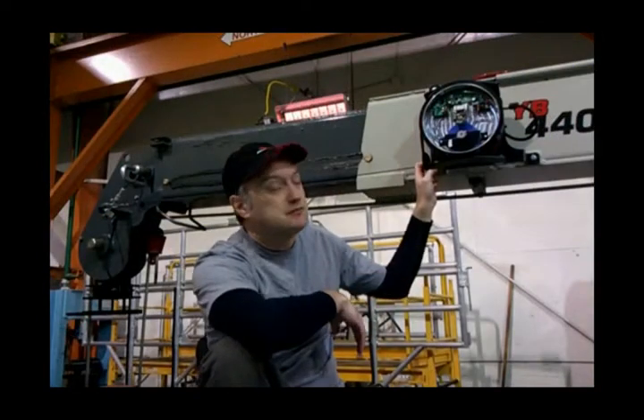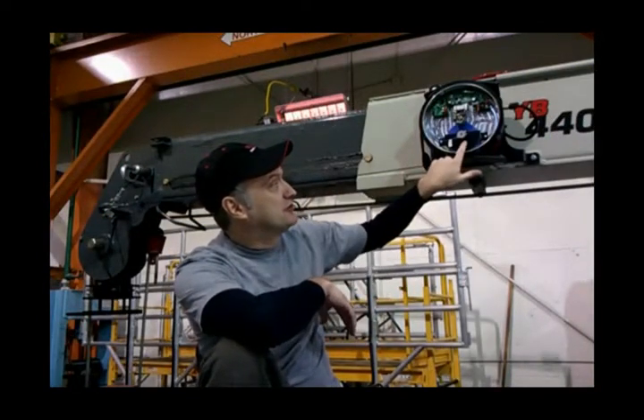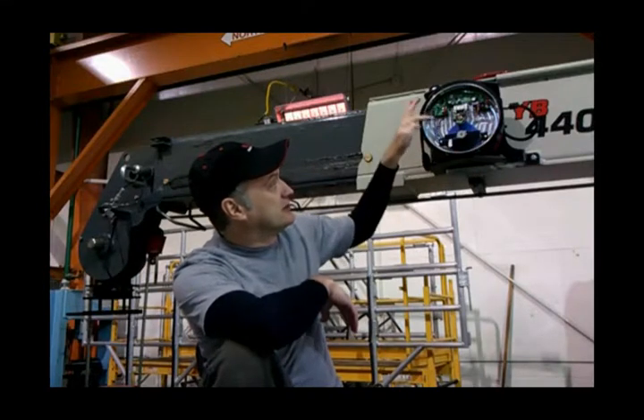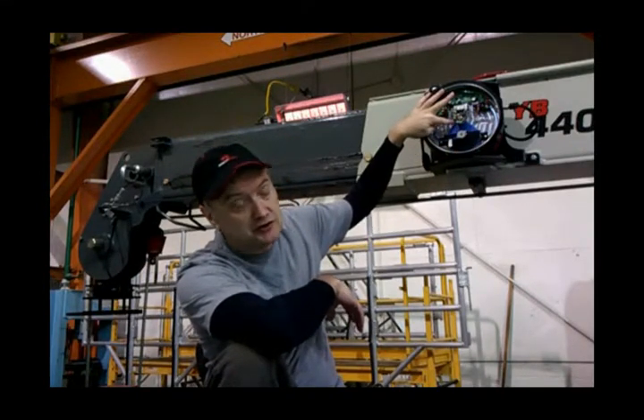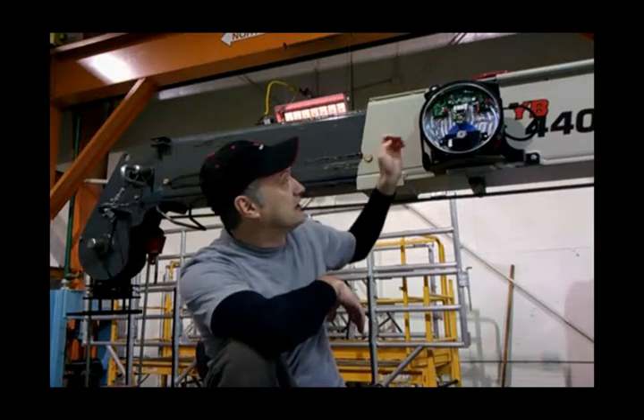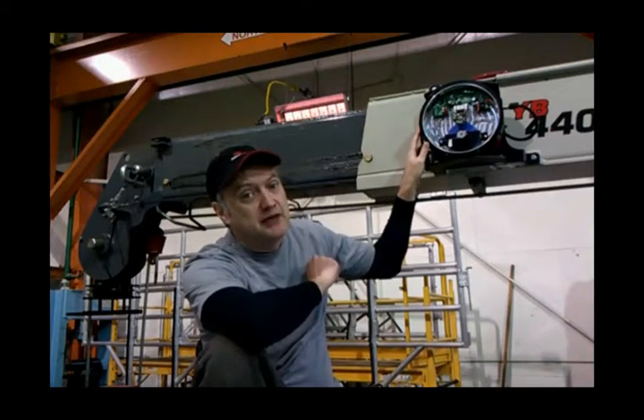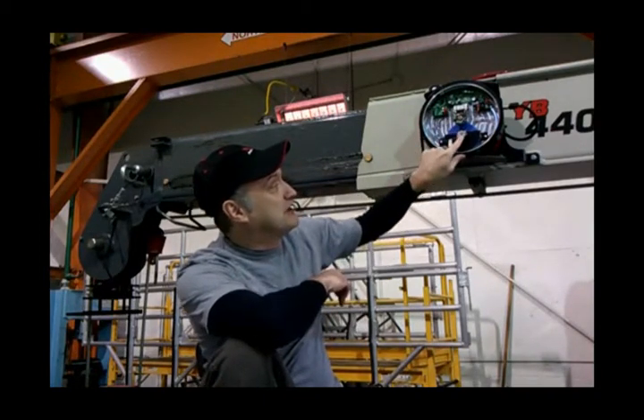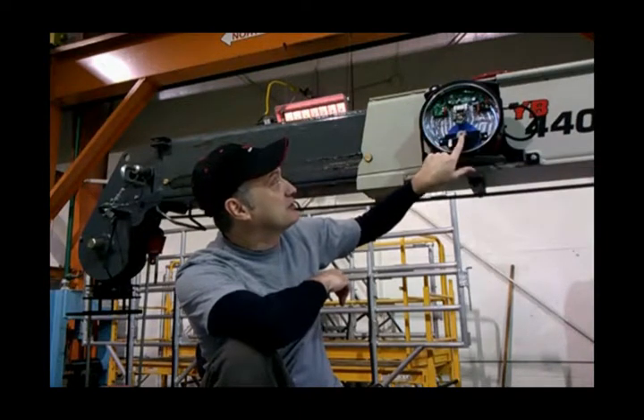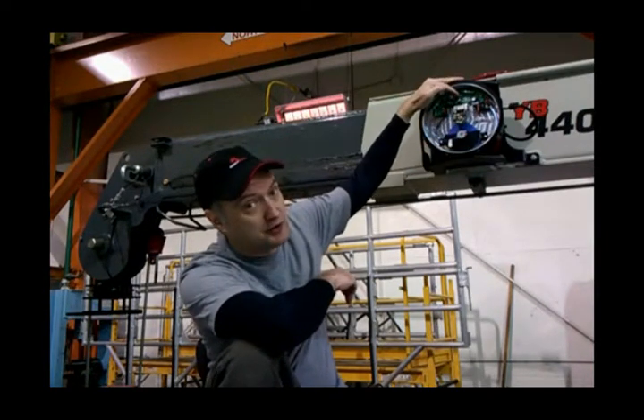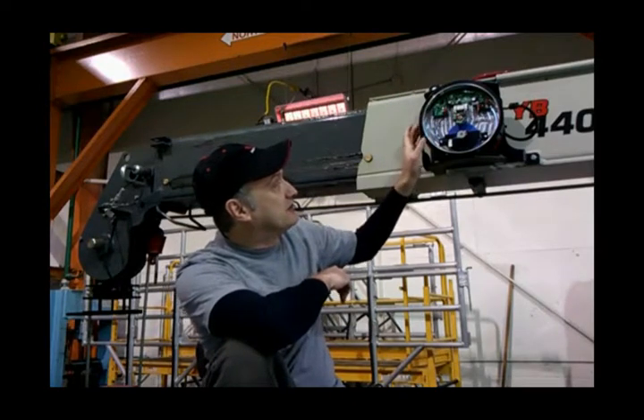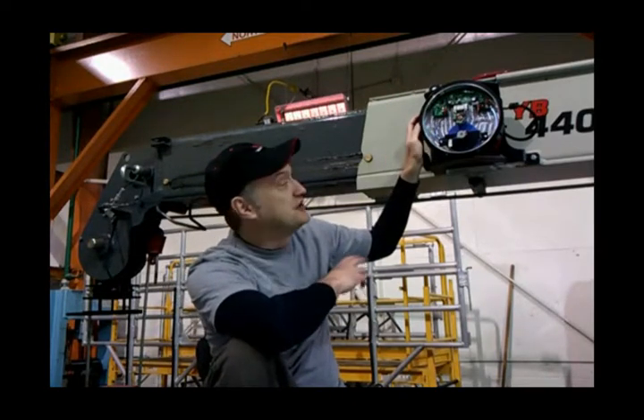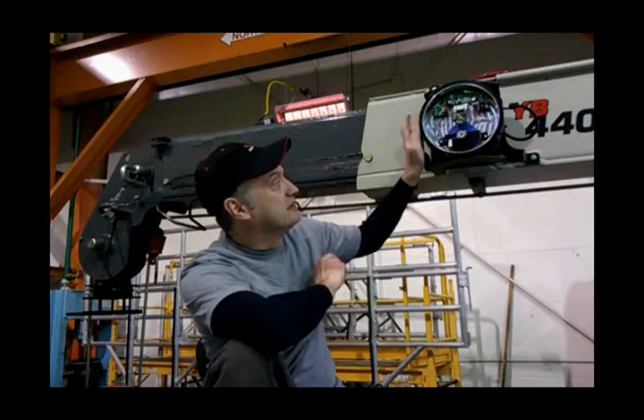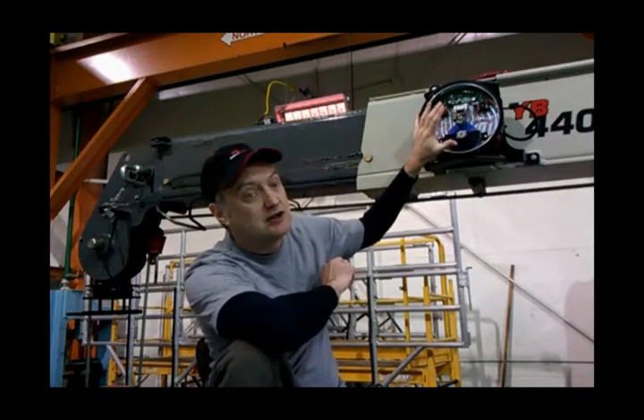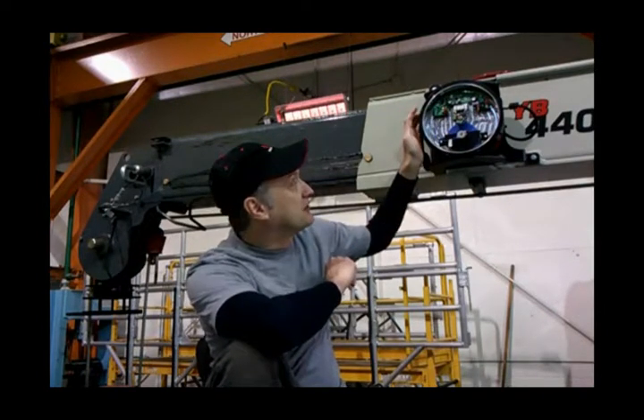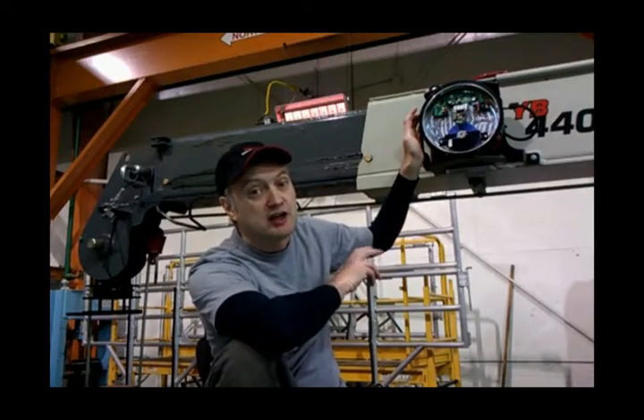Discuss the length calibration. The length potentiometer sits right here, and it spins this gear off of an internal shaft. When you would need to make this calibration is after you have replaced this potentiometer, or if you've replaced the circuit board. Now there is a method of making a length adjustment which doesn't require recalibrating if you have not replaced any parts. We're going to discuss that also. But first we're going to go ahead and cover the calibration itself.